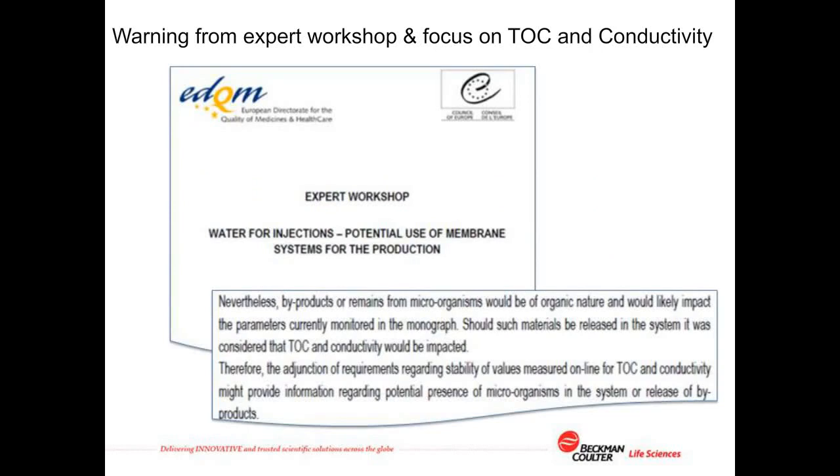The working group responsible for advising the European Directorate on their new water for injection monograph gave a warning that reverse osmosis may not be as robust as stills, and they encouraged a focus on online TOC and conductivity monitoring as early warning indicators of potential reverse osmosis integrity breaches.